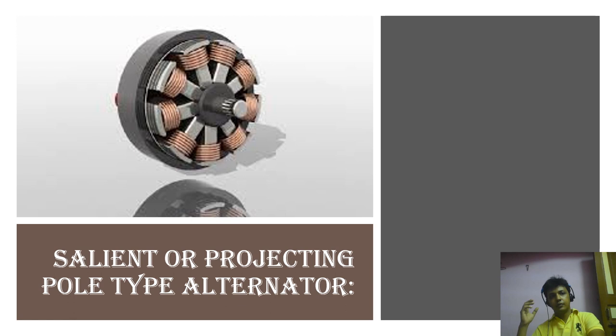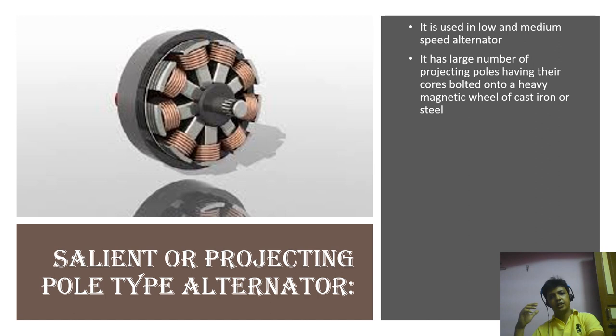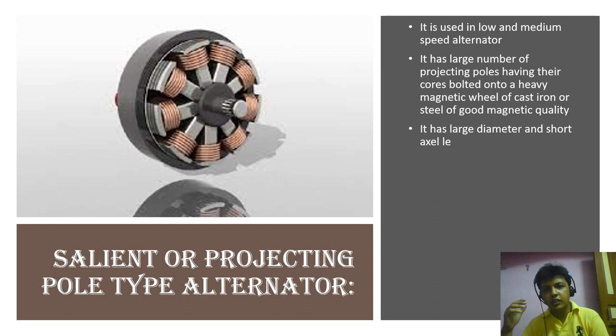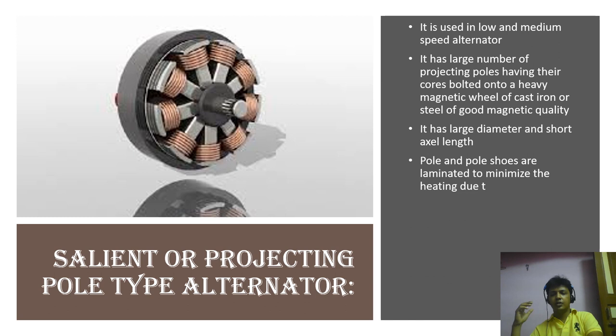Now we are going to discuss about salient pole or projecting pole types alternator. It is used in low and medium speed alternator. It has large number of projecting poles having their cores bolted onto a heavy magnetic wheel of cast iron or steel of good magnetic quality. It has large diameter and short axial length. Pole and pole shoes are laminated to minimize the loss due to eddy current. Where the speed is less, that is centrifugal force is low, mainly in water turbine, salient pole rotor is used.